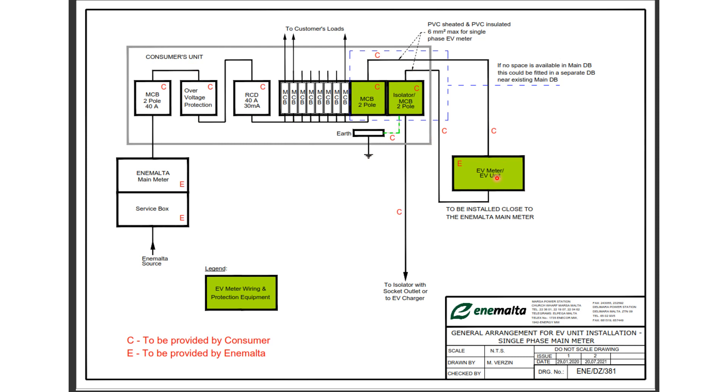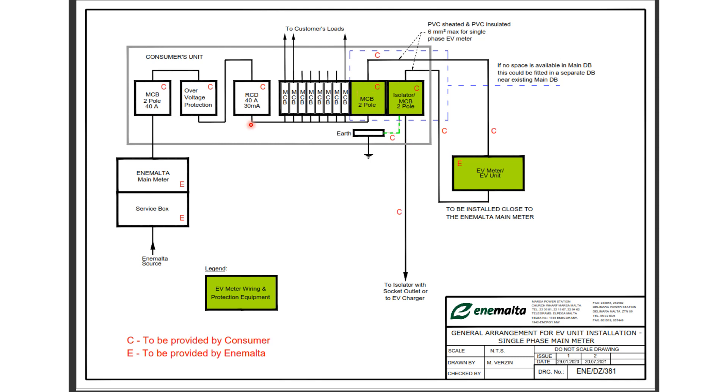Now just a minor recommendation. What we usually recommend is that instead of having a two pole MCB here, we use an RCBO. An RCBO is a residual current breaker with overload protection, and that will allow you to have the EV charging station in parallel with the rest of the installation.